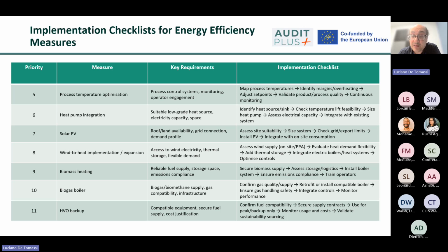Commissioning activities should demonstrate that the system performs safely and according to design intent. Key checks include mechanical completion verification, control system functionality testing, equipment startup and shutdown testing, safety interlock testing, control loop tuning and optimization, verification of operating sequences, operator training and documentation review. Examples include verification of heat recovery effectiveness under varying process loads, heat pump performance testing across expected operating ranges, solar PV generation verification against design output, biomass and biogas combustion performance testing, wind to heat control and thermal storage system testing.